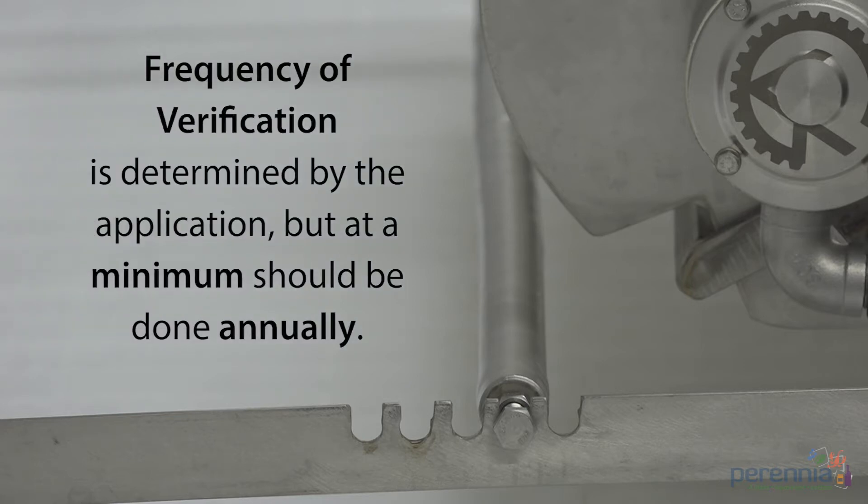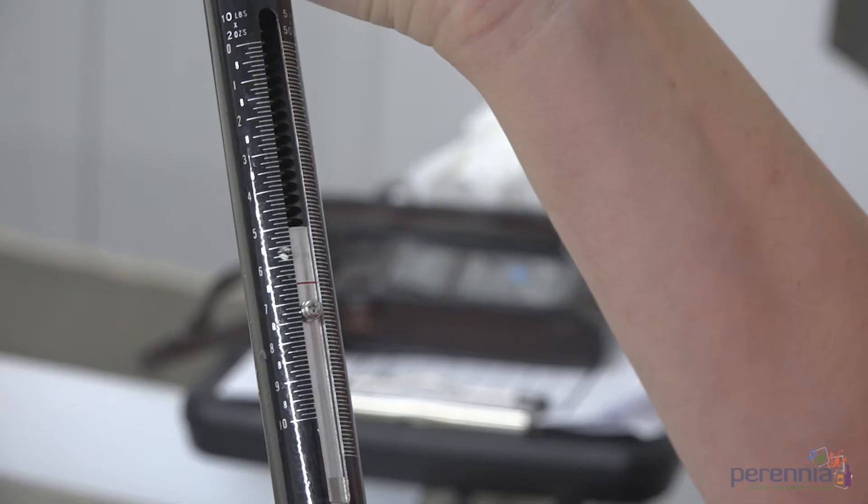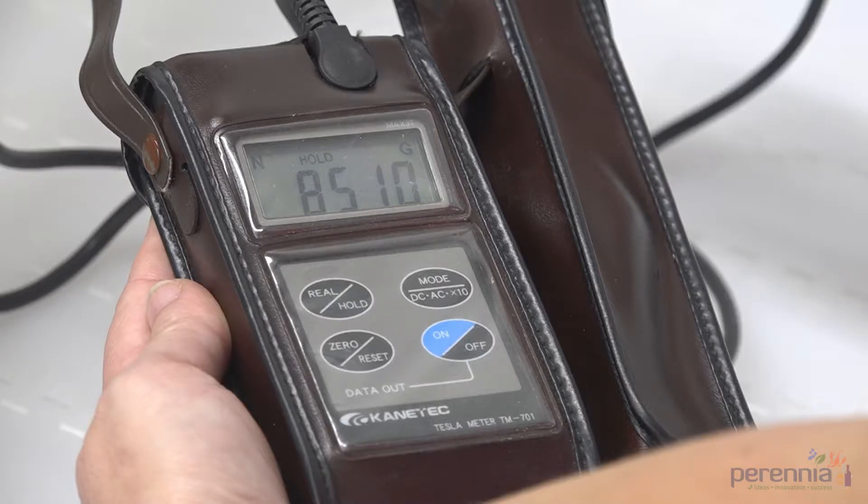The frequency of verification will depend on individual applications, but generally, at a minimum, annually. There are different types of test kits, such as mechanical scale, spring scale, or digital, which is the Gauss or Tesla meter.